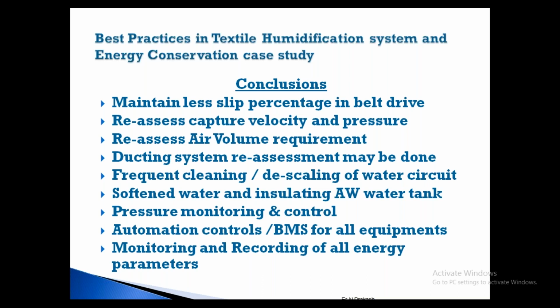We are seeing the floor grills, everything. In the factory, you will see there was an original design of 8 floor grills only. Somebody says here I want some air, some waste is going, so open that one, put one more grill. Finish. You spend some 2,000 rupees, put one more for 1,000 rupees, put one grill. Like that, they will be doing some temporary measures. So when you calculate, you see 10 grills, 12 grills will be there. These are all extra. Over a period of time, they would have painted. You will not know what is the original design, what was later. So reassess the entire recapturing. So you will know whether the velocity is proper or not. So if it is an existing plant, you can collect the drawing or you yourself calculate.